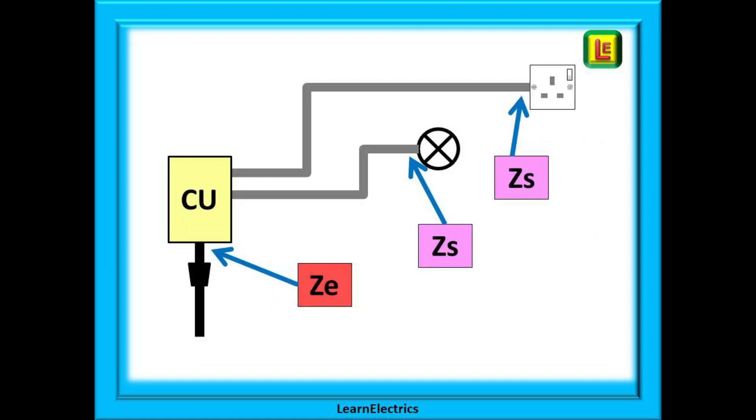Here we have a consumer unit with an incoming supply and we can measure ZE at the main switch of this consumer unit. Several circuits leave the consumer unit and go to the sockets, the lights etc. At each of these sockets, the lights, the cooker, the shower and so on we will measure ZS. We will have lots of ZS's but only one ZE in the property. So far so good.